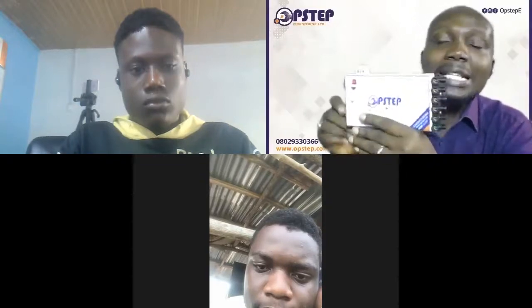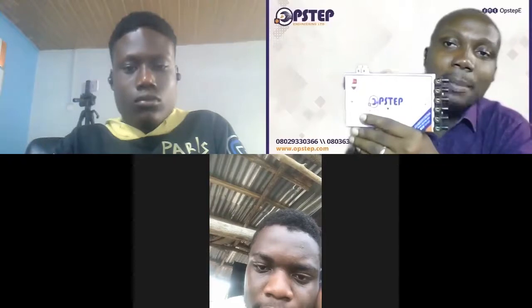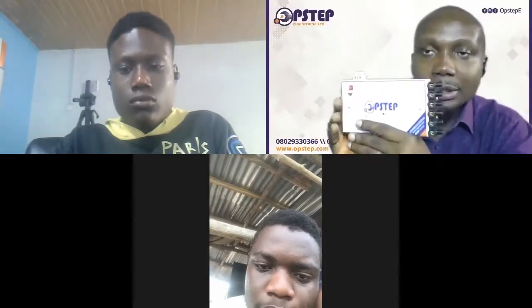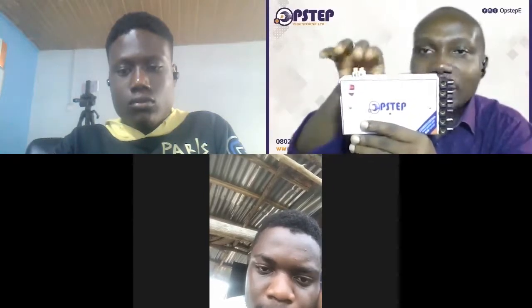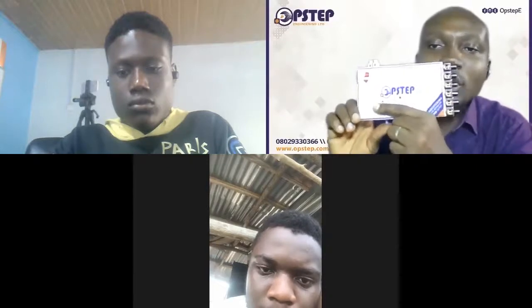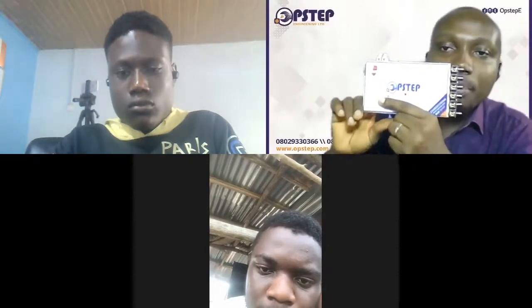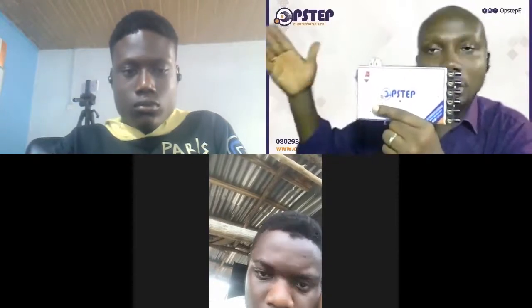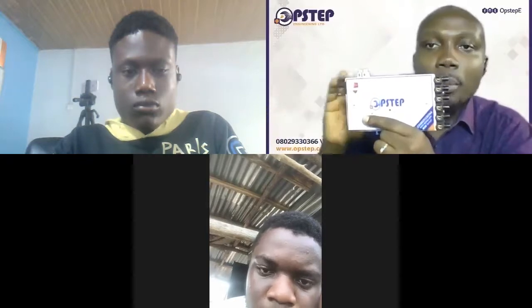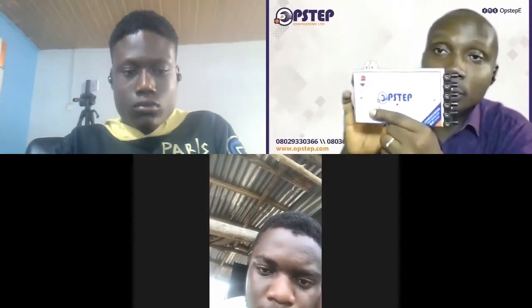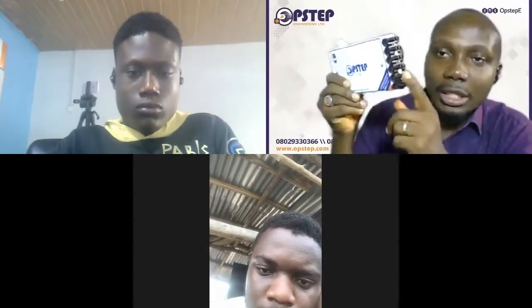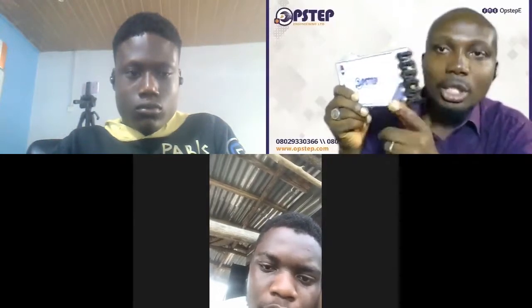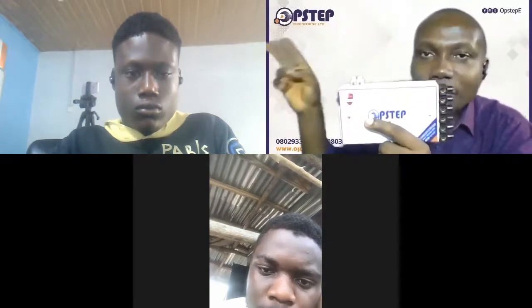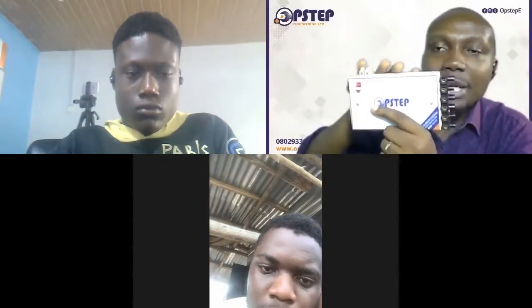We are saying that it's a 30 amp system on NEPA, 40 amp system on the generator side. Don't forget that. It has an automatic shutdown, and this is where you tap the automatic shutdown. You can also have your own manual shutdown without going to the generator set by pressing this button down. Of course, you can also go to the generator set to do the shutdown. But don't forget that for this system to work optimally, you will have to connect NEPA input here, generator input here, and your house on the top part. You also have to connect your generator switch, get 2 wires from the generator switch to this place. That is when the system can work effectively.